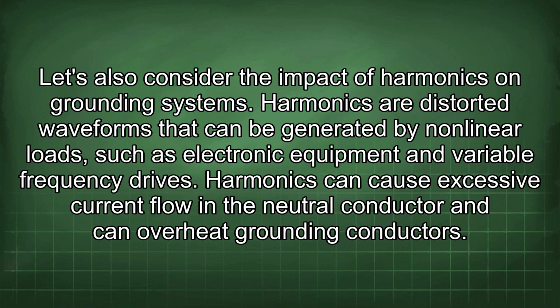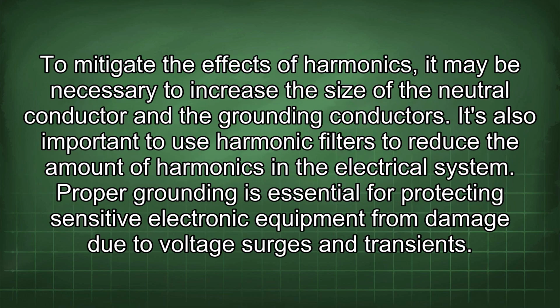Let's also consider the impact of harmonics on grounding systems. Harmonics are distorted waveforms that can be generated by nonlinear loads, such as electronic equipment and variable frequency drives. Harmonics can cause excessive current flow in the neutral conductor and can overheat grounding conductors. To mitigate the effects of harmonics, it may be necessary to increase the size of the neutral conductor and the grounding conductors. It's also important to use harmonic filters to reduce the amount of harmonics in the electrical system.